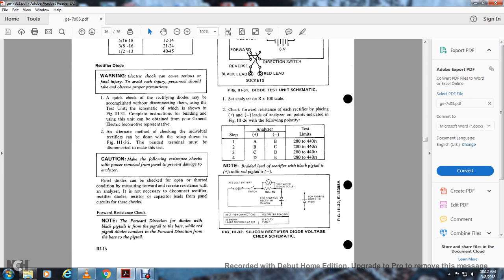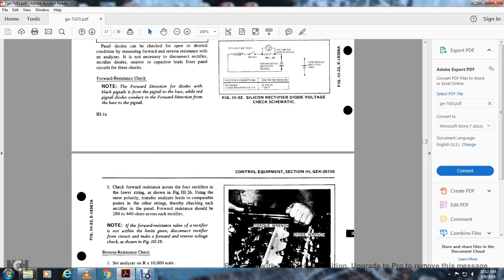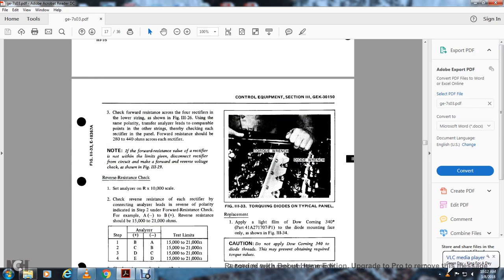Figure 3-32, silicon rectifier diode voltage schematic: 22.5 volt battery, switch, a voltmeter, and the negative rectifier, black. Check the forward resistance of each rectifier as shown in figure 326, with the same polarity, and compare the lead points with the other string. The forward resistance should be 280 to 440 ohms across each rectifier.